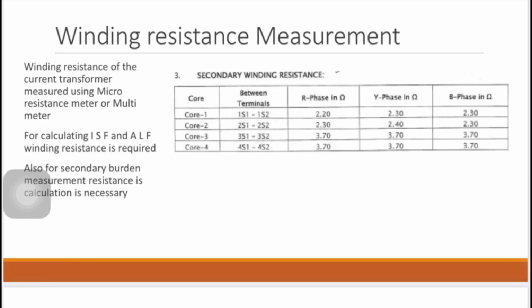The main thing is the voltage drop of the secondary circuit: the drop across the load, which is any instrument, and the drop in the loop, which is the secondary resistance of the CT, the resistance of the wiring, and the resistance offered by the load.